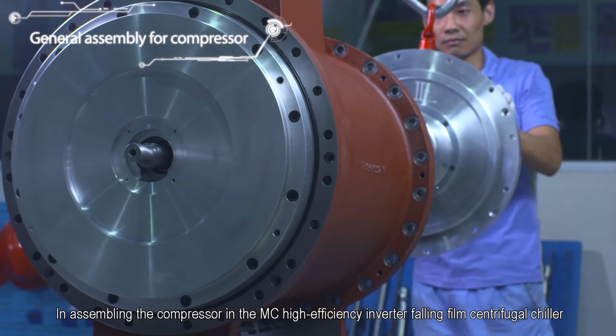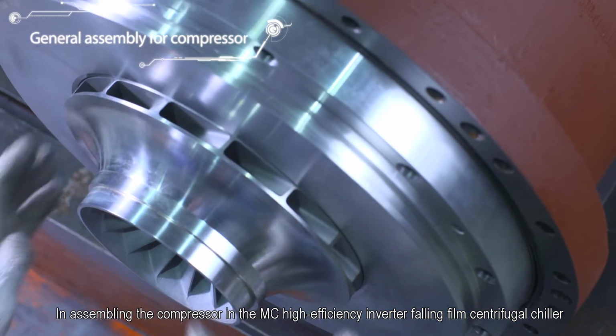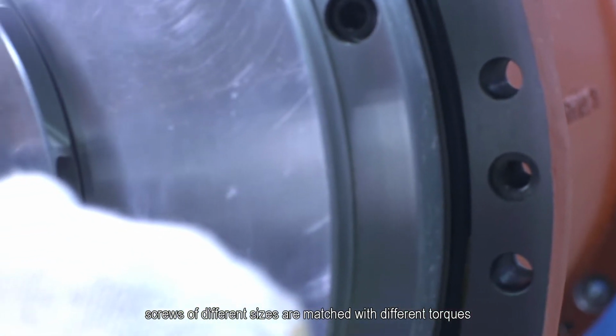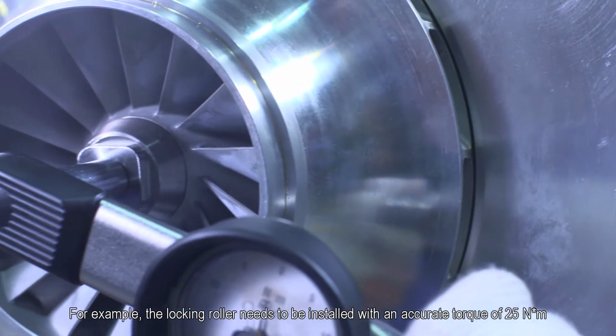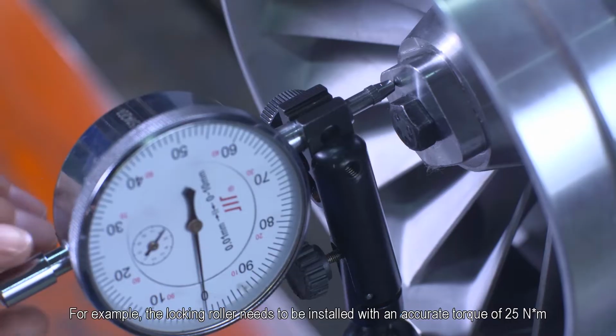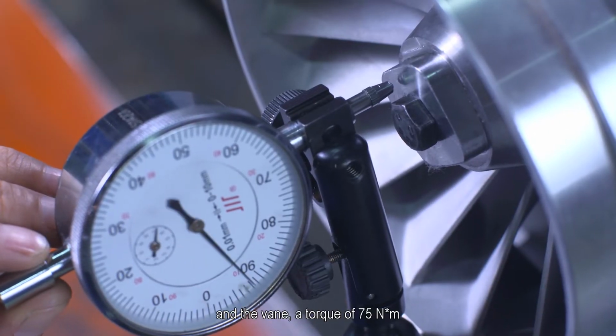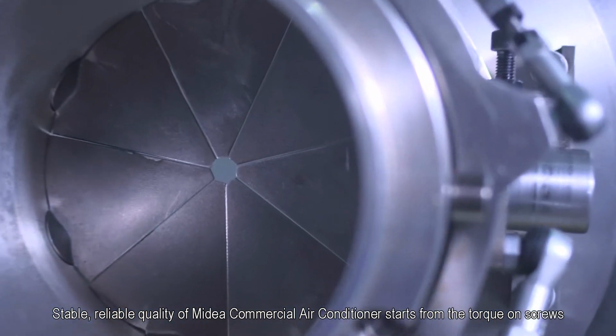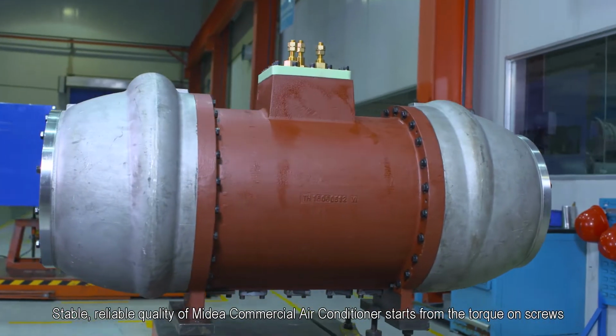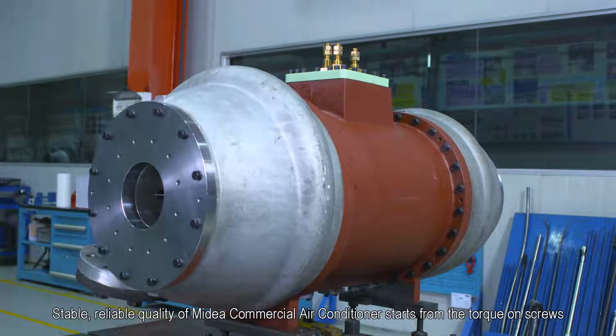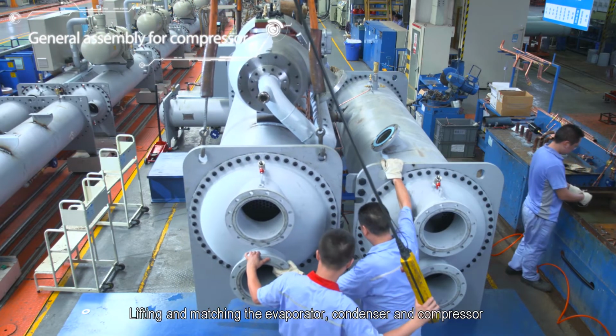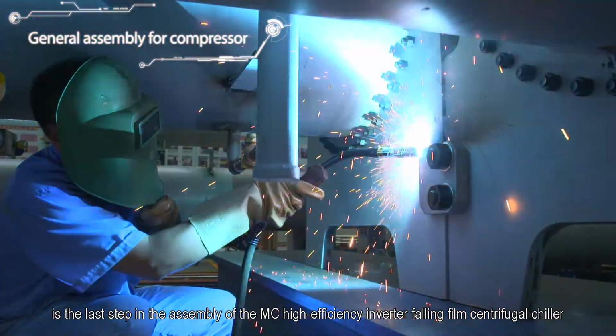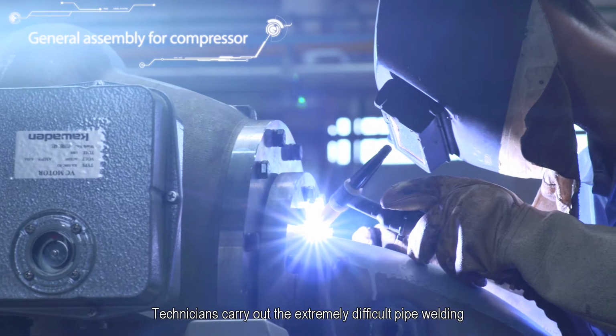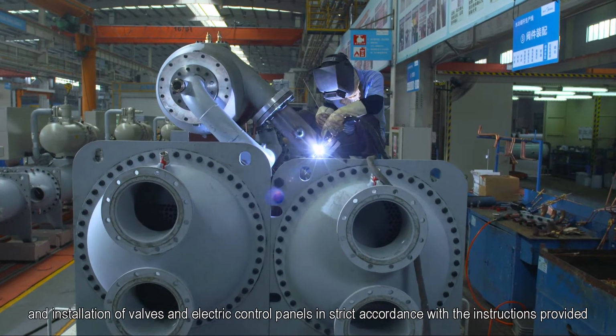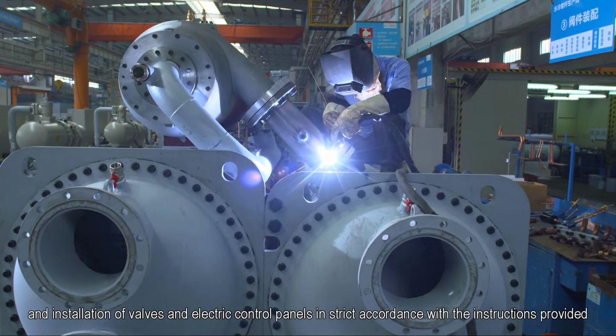In assembling the compressor in the MC high-efficiency inverter falling film centrifugal chiller, screws of different sizes are matched with different torques. For example, the locking roller needs to be installed with an accurate torque of 25 newton meters, and the vane a torque of 75 newton meters. Stable, reliable quality of Midea commercial air conditioner starts from the torque on screws, beyond just any lip service. Lifting and matching the evaporator, condenser, and compressor is the last step in the assembly of the MC high-efficiency inverter falling film centrifugal chiller. Technicians carry out the extremely difficult pipe welding and installation of valves and electric control panels in strict accordance with the instructions provided.